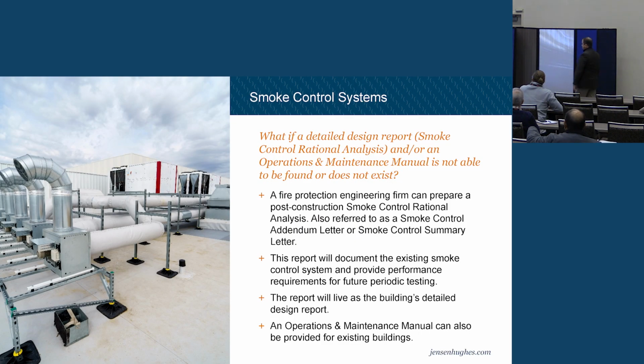Okay, what if a detailed design report isn't available? What if that original design documentation can't be found? You can contact firms like ours, it doesn't have to be mine, but a consulting firm. They can come out, assess your building, and look at what the code requirement is. I can walk into most buildings and within 5 minutes tell you, you need stairwell pressurization, your elevator lobbies need to be closed in. That's what we do every day. We are nerds. So you can have a company assess it.